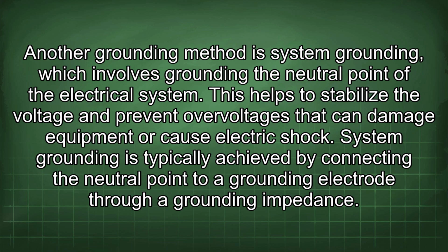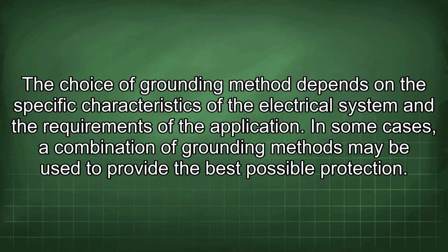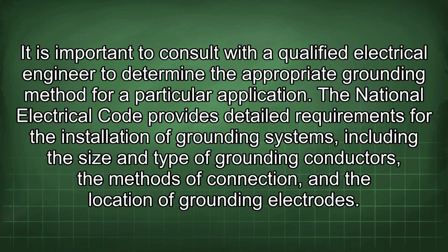Another grounding method is system grounding, which involves grounding the neutral point of the electrical system. This helps to stabilize the voltage and prevent overvoltages that can damage equipment or cause electric shock. System grounding is typically achieved by connecting the neutral point to a grounding electrode through a grounding impedance. The choice of grounding method depends on the specific characteristics of the electrical system and the requirements of the application. In some cases, a combination of grounding methods may be used to provide the best possible protection. It is important to consult with a qualified electrical engineer to determine the appropriate grounding method for a particular application.